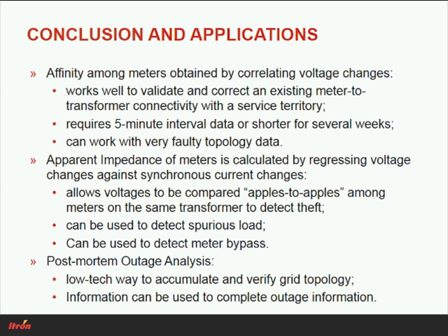If a group of meters is consistently half a volt below that of other meters, we correct for that bias, not only because of unmetered loads, but because the absolute voltage measurement in meters is not likely to be quite that accurate. It would not be unusual to find a systematic error of maybe up to a half volt. So we don't pay much attention to long-term changes like that, but to the short term.